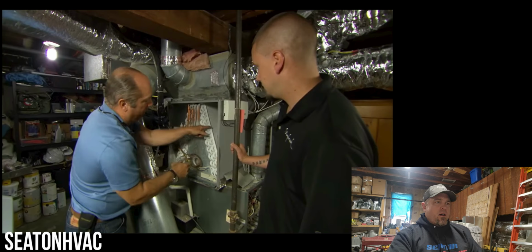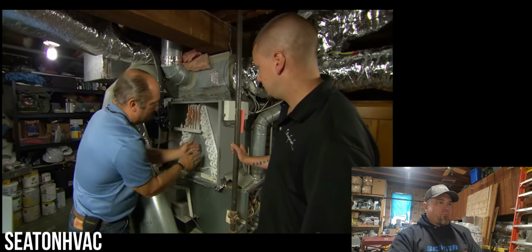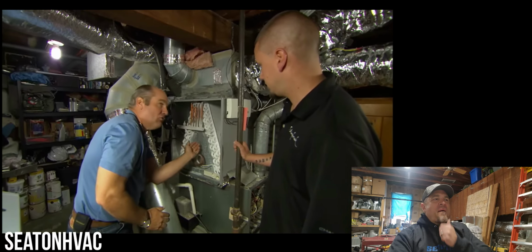I don't know. Rich is pretty short, so maybe that is a 33. I'm not sure. But it looks like he has some sort of zoning. See that panel there that's mounted? You should never mount a zoning panel to an evaporator coil, but they did. He's got some sort of zoning on this as well, which they did not address. And that needs to be addressed as well, because very few companies do zoning properly. Once this thing freezes, no longer can that air even get through those fins. Exactly what happened to you will happen. So what would cause this? Well, I think I know what the answer is, but let's check one more thing outside.